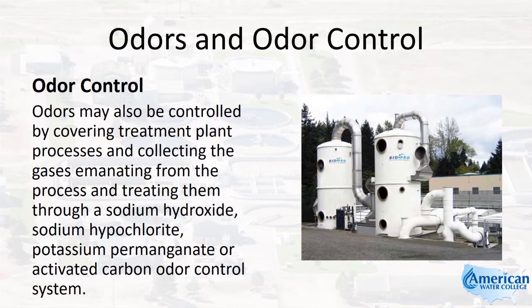Odors may also be controlled by covering treatment plant processes and collecting the gases emanating from the process and treating them through a sodium hydroxide, a sodium hypochlorite, a potassium permanganate, or activated carbon odor control system.